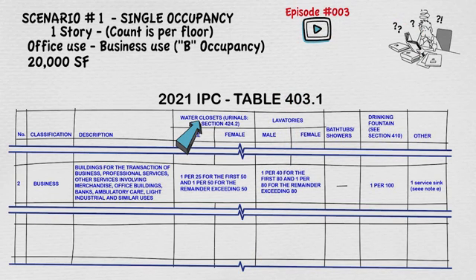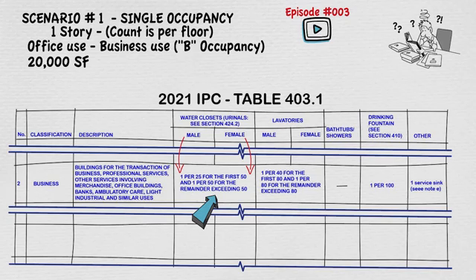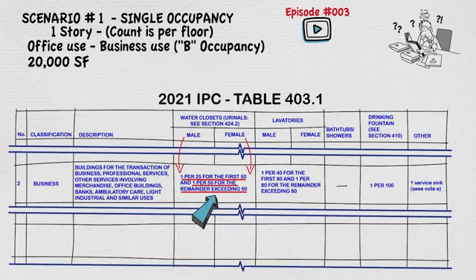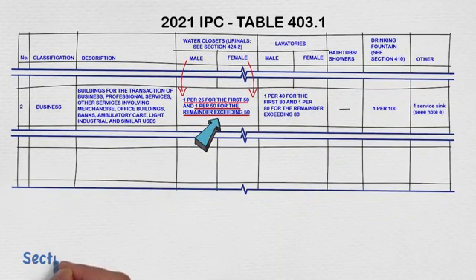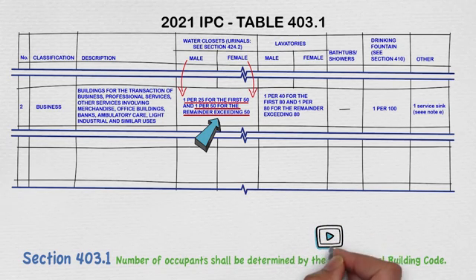The next column to the right references the number of water closets, divided into male and female. In this case, the requirements are the same for male and female. An office building requires one water closet per 25 occupants for the first 50, and one water closet per 50 occupants for the remainder that exceed 50. Section 403.1 of the Plumbing Code states that the number of occupants shall be determined by the International Building Code. See ArchiCorner episode number 10 for details.